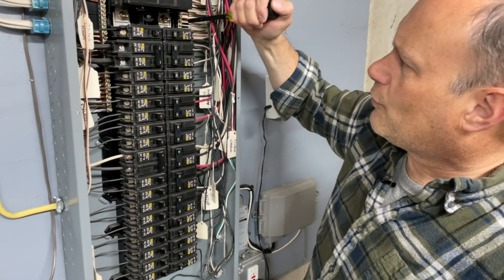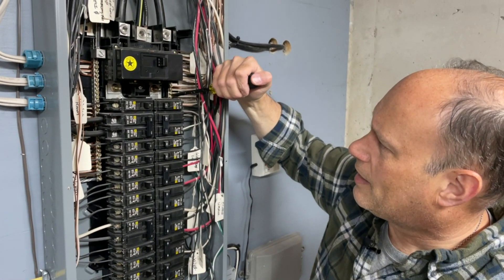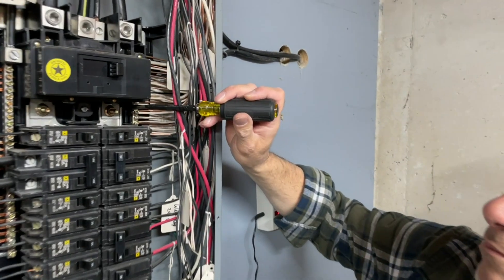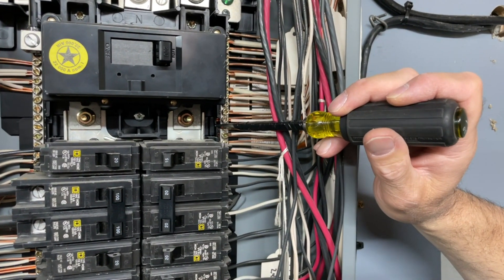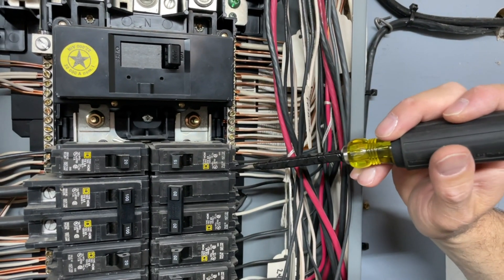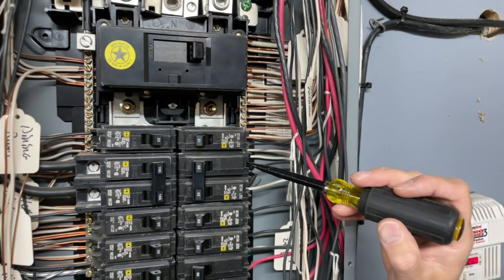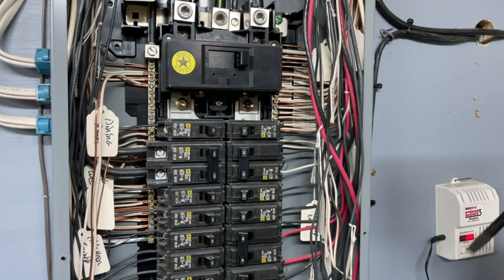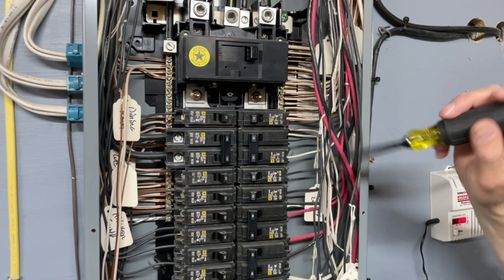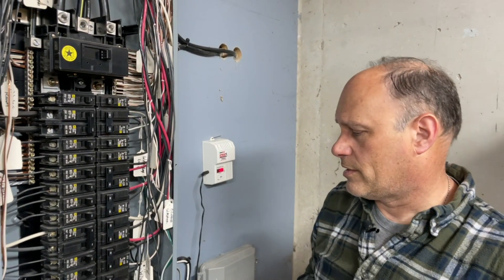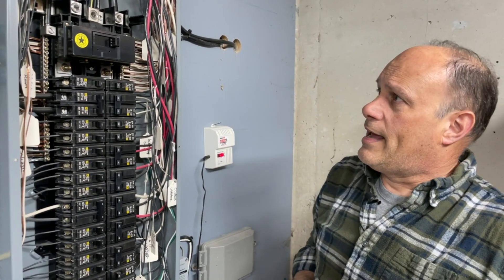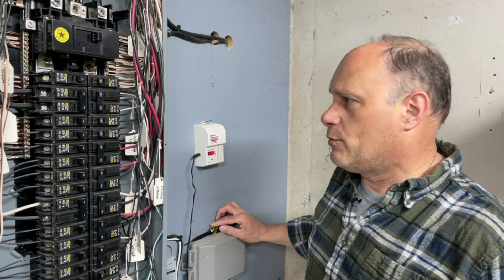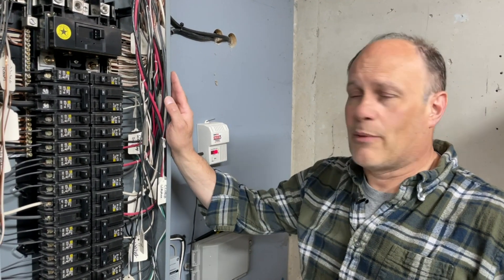And you want to be insulated. You want to be careful, because if you're over here and you slip out of the slot, this is the bus bar. So that's live 120 volt. To be on the safe side with the circuit breakers, I did this hot. I would shut the main off and have a headlamp and I would go through and tighten all these connections with the power off. That's the best way to do it. The safest way to do it. And once I exhausted that avenue, that would be the end of any time I would spend it here.